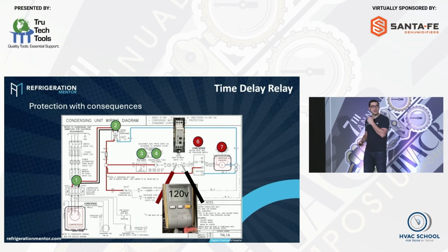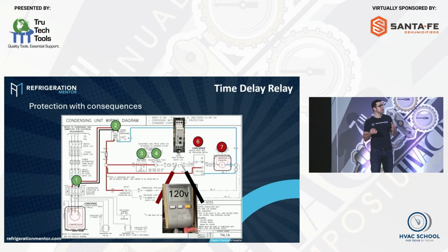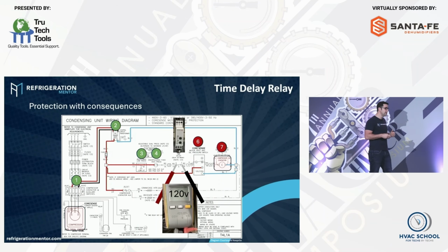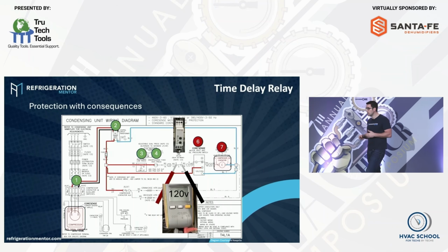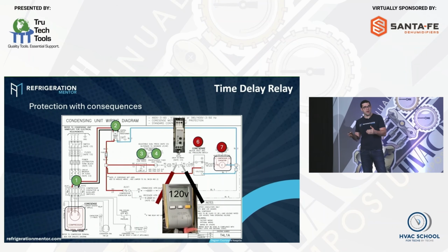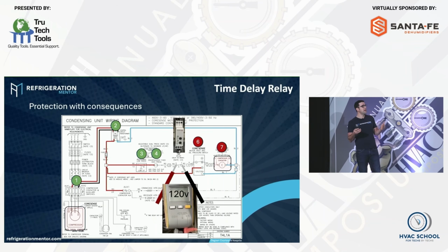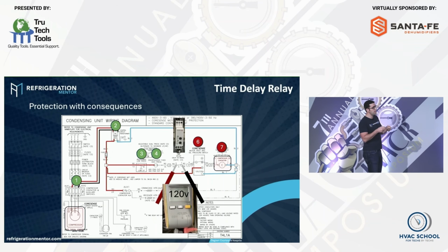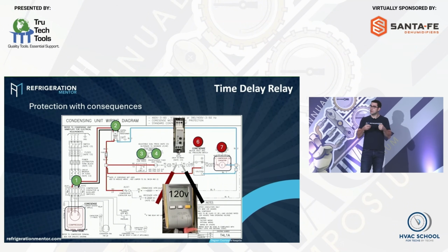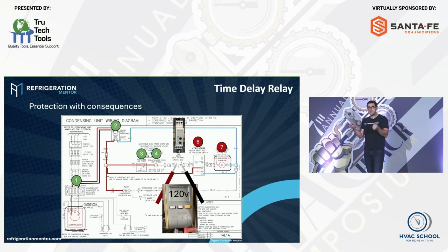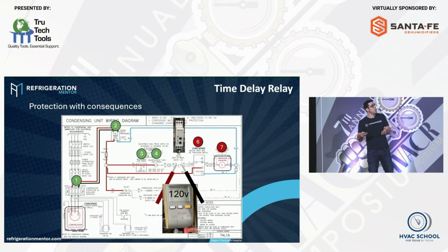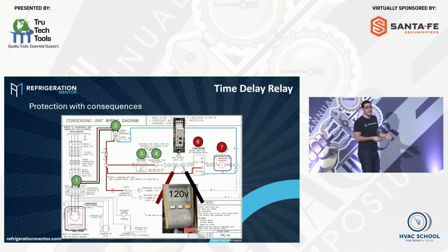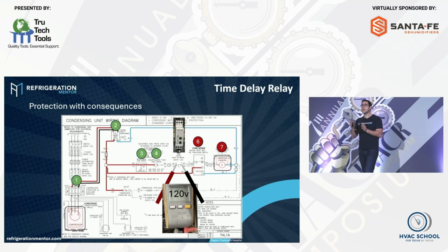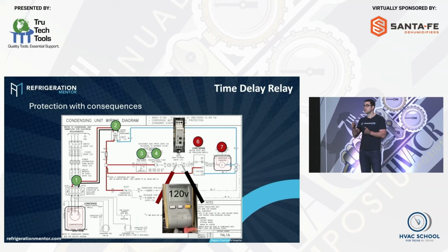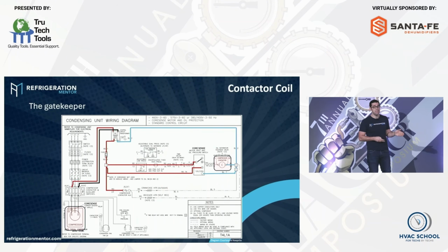The time delay relay tricks up so many people. I've seen it time and time again, taking calls and talking to technicians in our training programs. Like I remember one in our CO2 program where a technician said, hey, I got a phase monitor failure. So they go up and reset the unit, and they go across and they've got all their phases, the proper voltage, but it's still off. The thing was, it was the time delay that failed. And so what do these do? Before they do the trip, you set them up. It could be 2 seconds, 10 seconds, 2 minutes on the time delay before it makes that action happen.